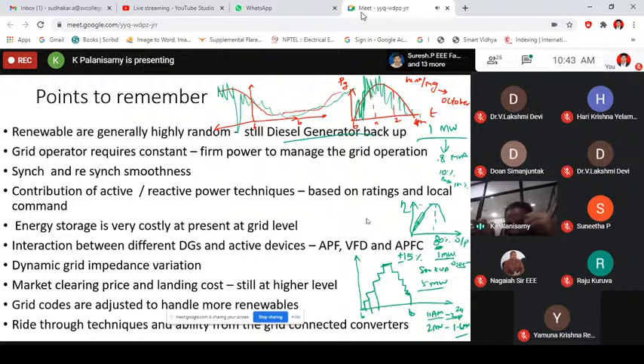So what I will do, I will reconfigure the power system in such a way. Maybe I will disconnect the northeast feeder, or I will send an appropriate signal to the sources sitting near the northeast corner, and I will help the system to ride through, right? All those things should be done. That's the kind of phasor measurement unit signal, right? So when you see the variation of the phasor, you must take appropriate action and issue commands or signals to the individual operators, individual small operators.